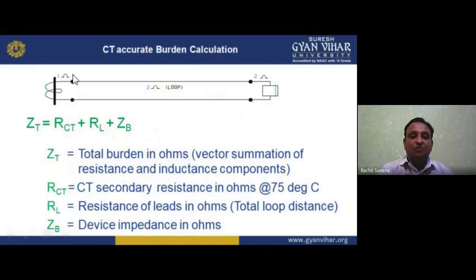Now, CT accurate burden calculation. How can we identify it? See here, 1 ohm is connected here and 2 ohm is there. So ZT is equal to RCT plus RL plus ZB. What is RCT, what is RL, what is ZB? ZT is the total burden in ohms, the vector summation of the resistance and inductance components. RCT is the CT secondary resistance in ohms at 75 degrees centigrade. The maximum temperature we consider is 75 degrees centigrade, because there will be some temperature rise. RL is the resistance of the leads in ohms, because we are calculating the burden, so leads are there. It is the total loop distance resistance, given here as 2 ohm. And ZB is the device impedance in ohms. So ZT is equal to RCT plus RL plus ZB.